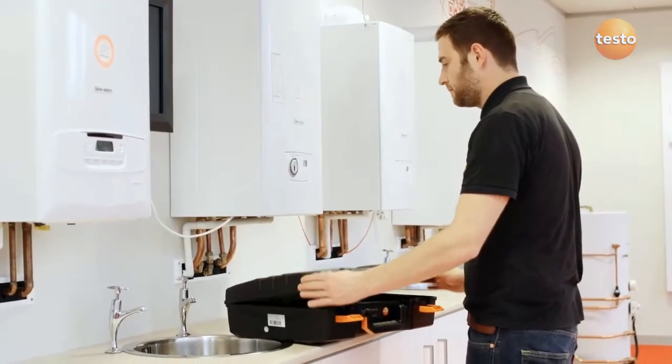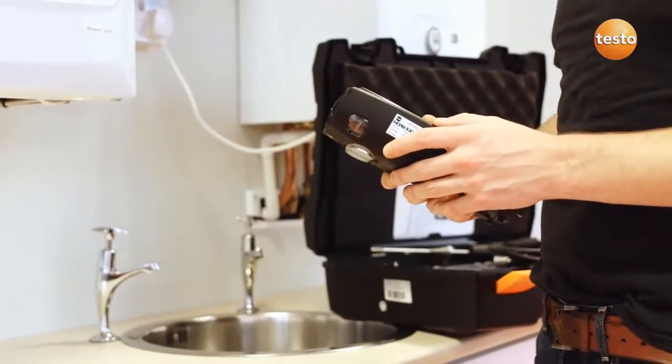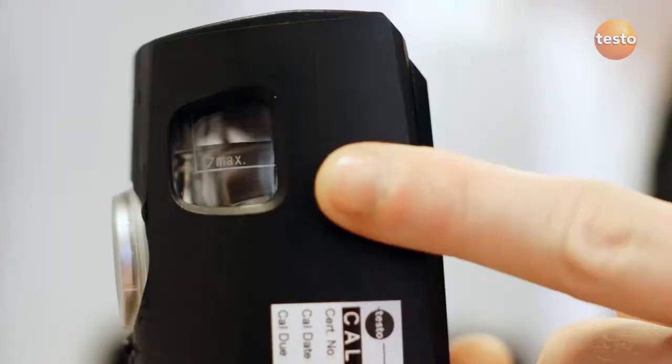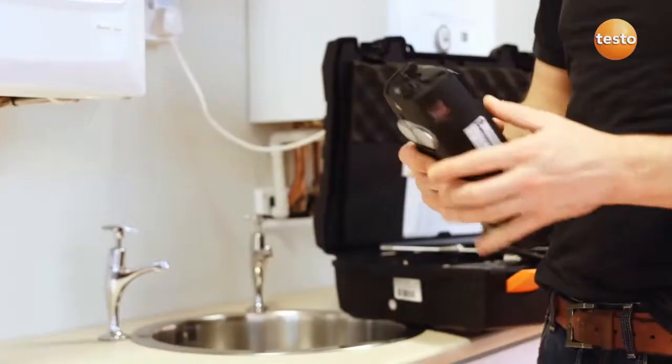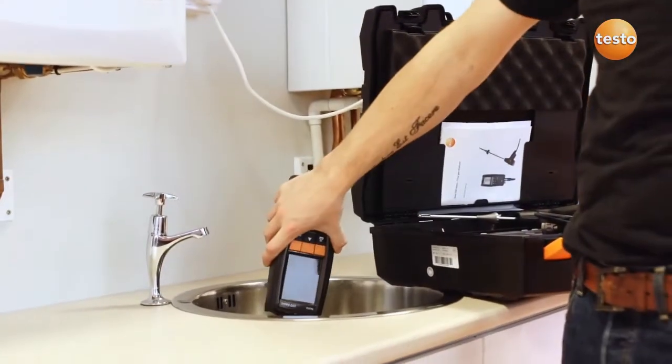The 320B is a good quality rugged instrument. It's easily maintained with a couple of simple checks and annual calibration. Remember to always check the condensate trap before measuring — water can damage the sensors, so don't operate the analyser if it's full of water.